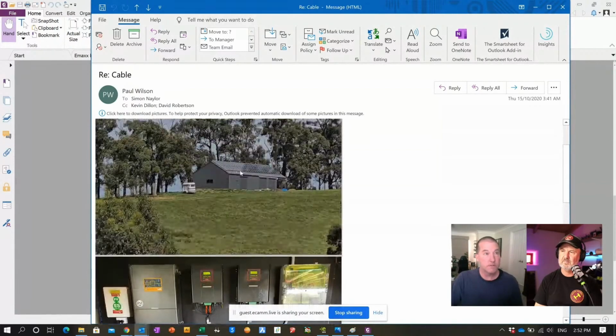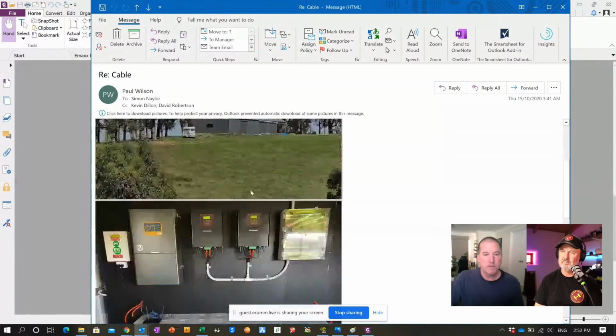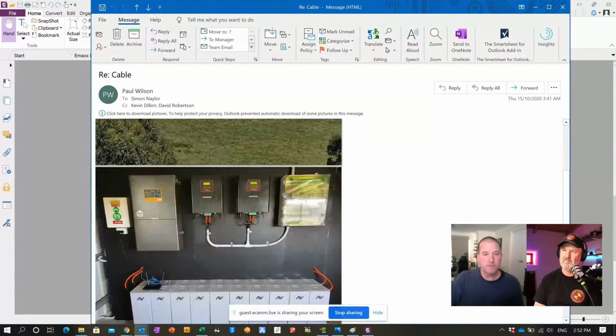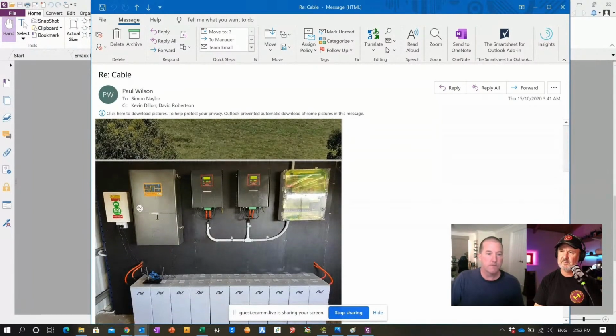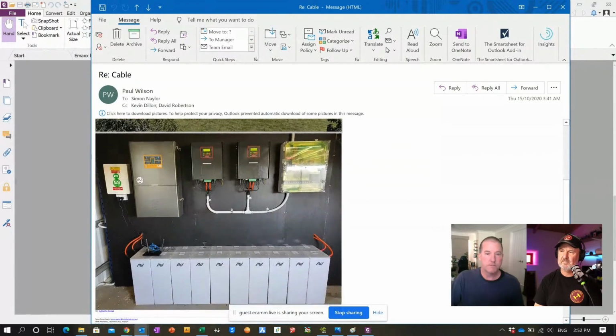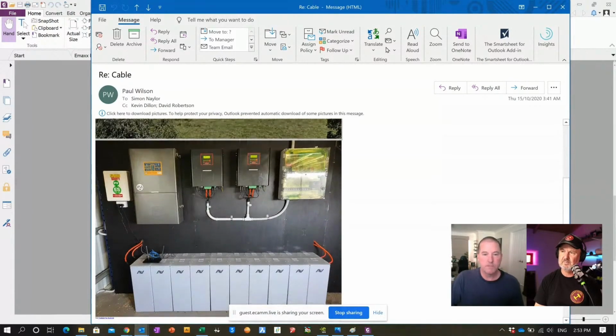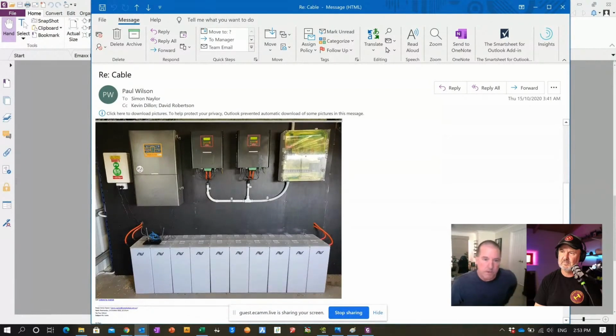It's 20 kilowatt hours worth of storage, 20 kilowatt hours worth of PV, feeding into 5 MPPT strings on these two charge controllers, 2 in parallel and 1 each for the other ones. And then they've got the 15 kilowatt SP Pro on the left over here. So this is a whole turnkey system. The Emacs you can see on the bottom here behind the 4G modem, and then just your power board on the left over there. So that's a typical installation, off-grid, tons of power, 30 kilowatt AC peak, 15 kilowatts continuous, 20 kilowatts of PV with 20 kilowatts worth of charge control power.